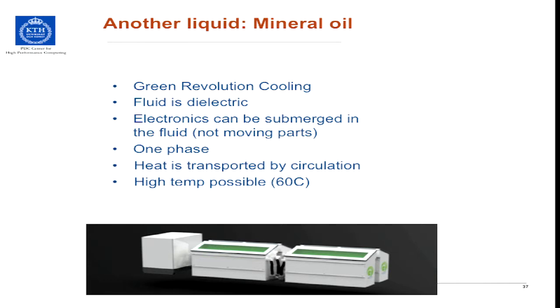Mineral oil is good because it doesn't destroy the electronics, but moving parts have to be taken away. For example, if you have a fan, or a moving disk which is not completely sealed, that has to be removed. But the cooling is really good, and you can get really hot temperatures out of this.